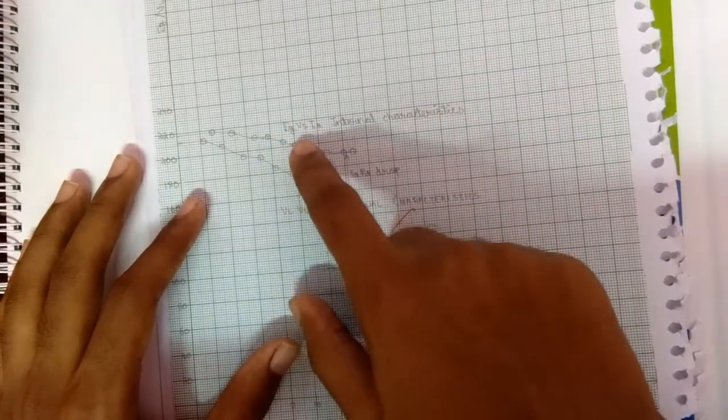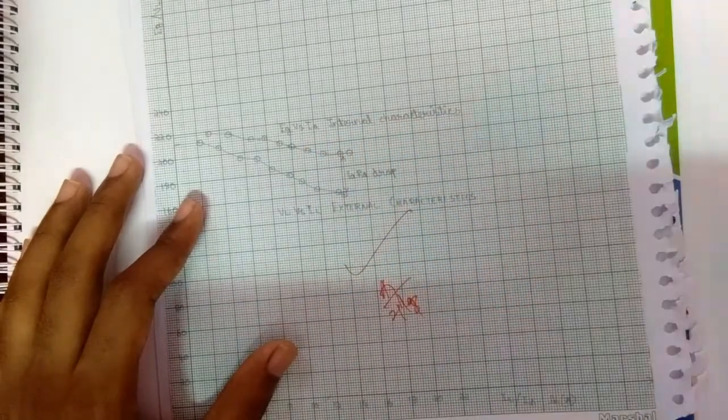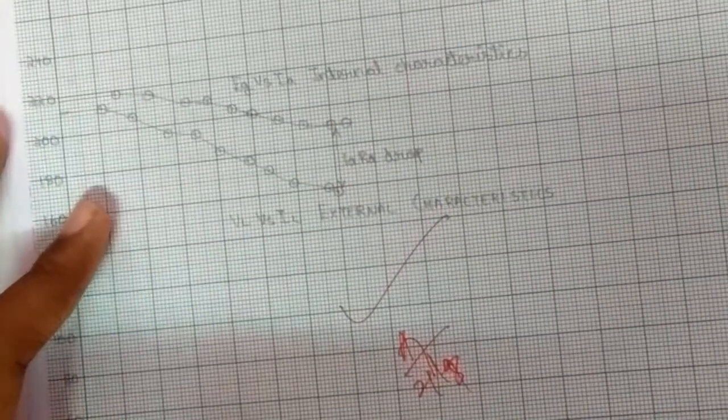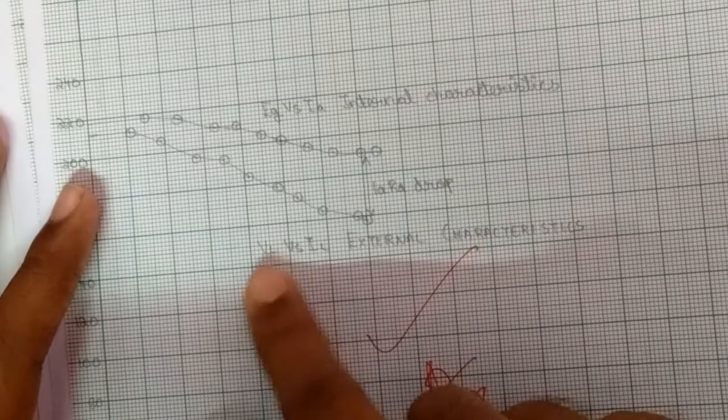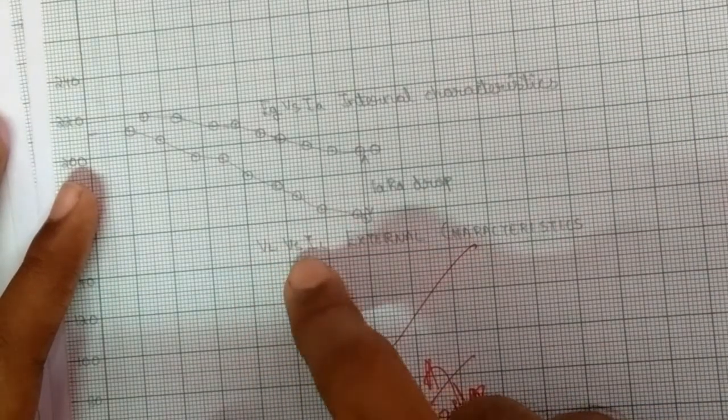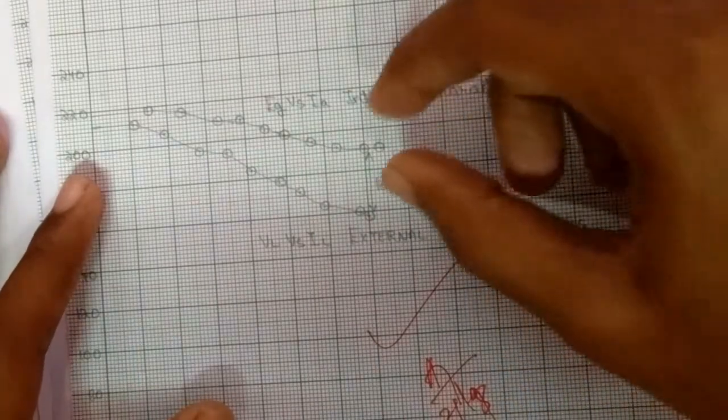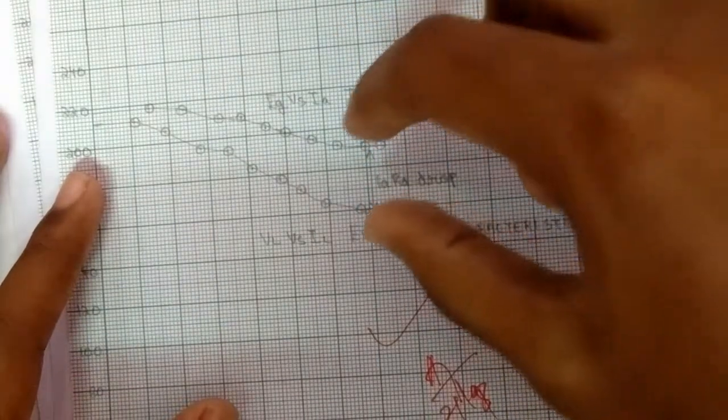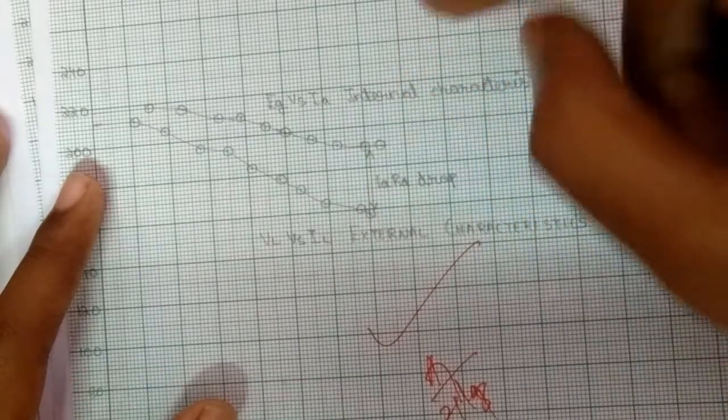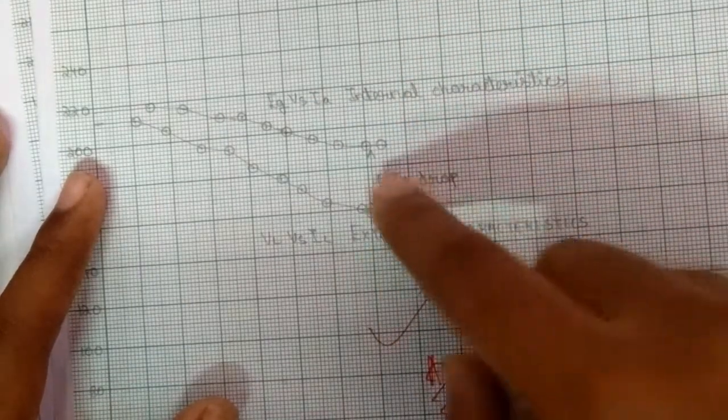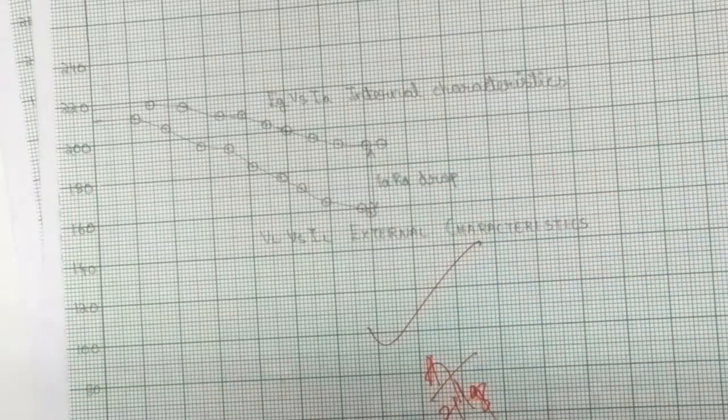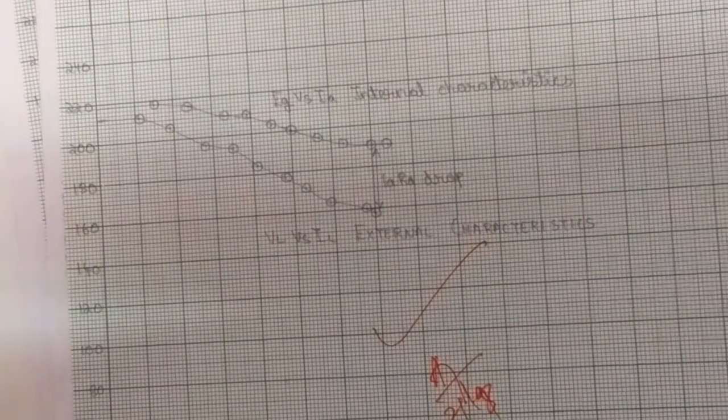We have to draw two curves: one is between EG versus IA, which is the internal characteristics, and the second will be VL versus IL, which is the external characteristics. The difference between the internal characteristics and external characteristics will be the IA*RA drop value. With these two graphs, the experiment is over.